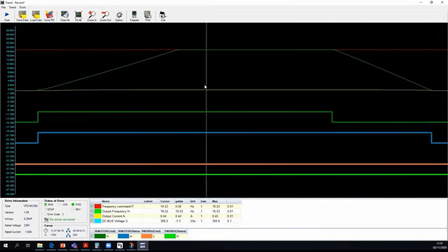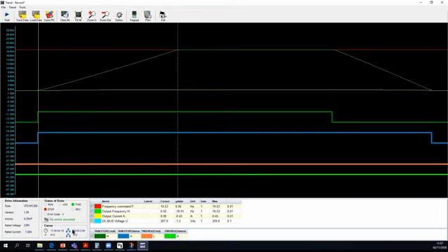You can see the acceleration ramp, and you can also monitor how long it takes between two different points. You can see this on this side here. You can see from 0 Hertz to 19 Hertz. It took around 4 seconds. You can see that here.